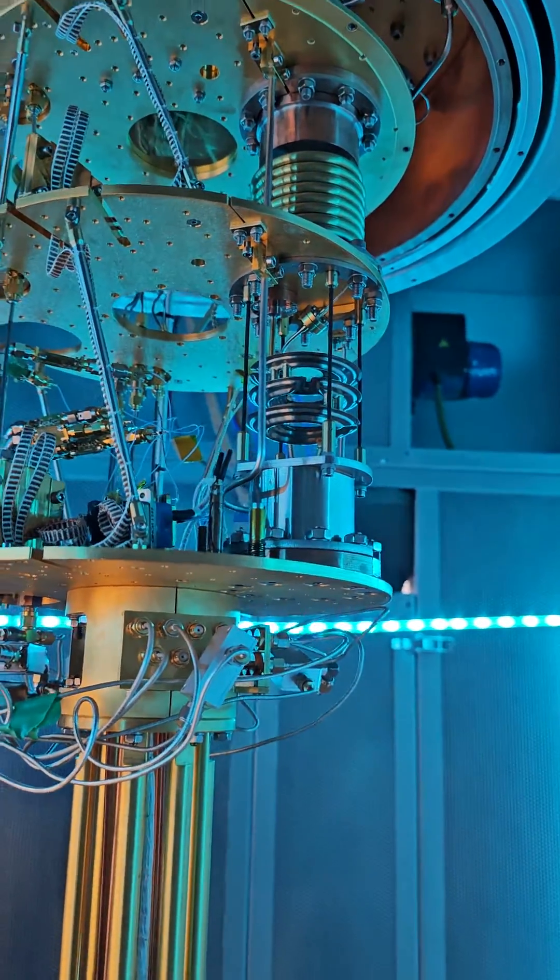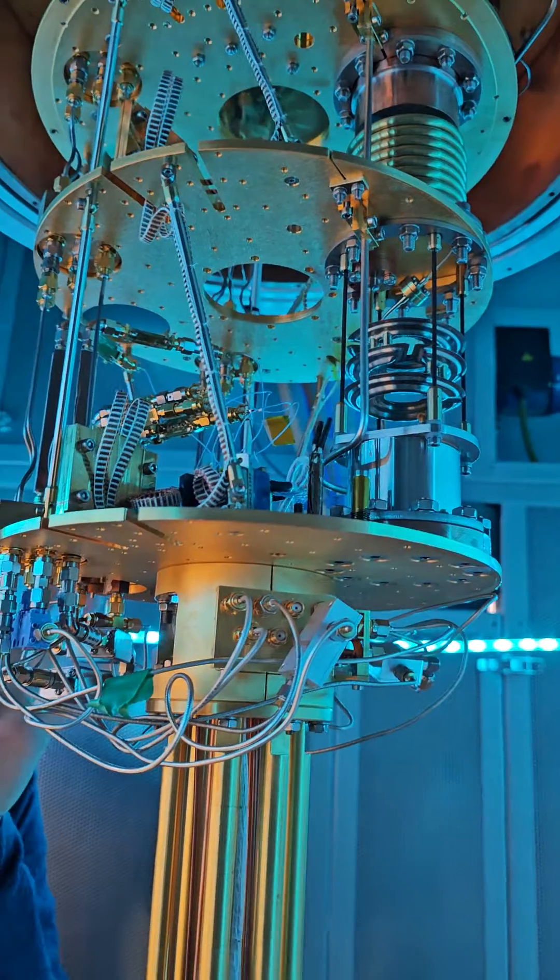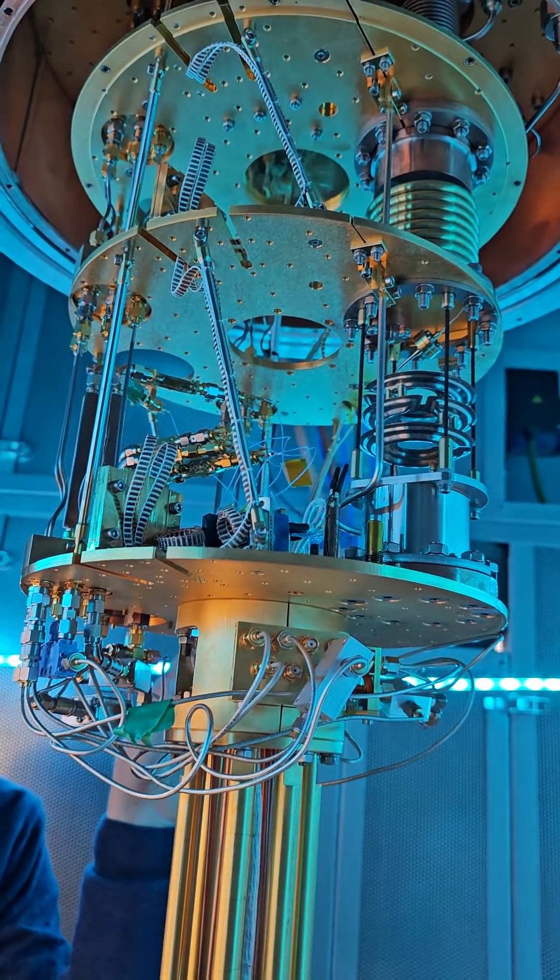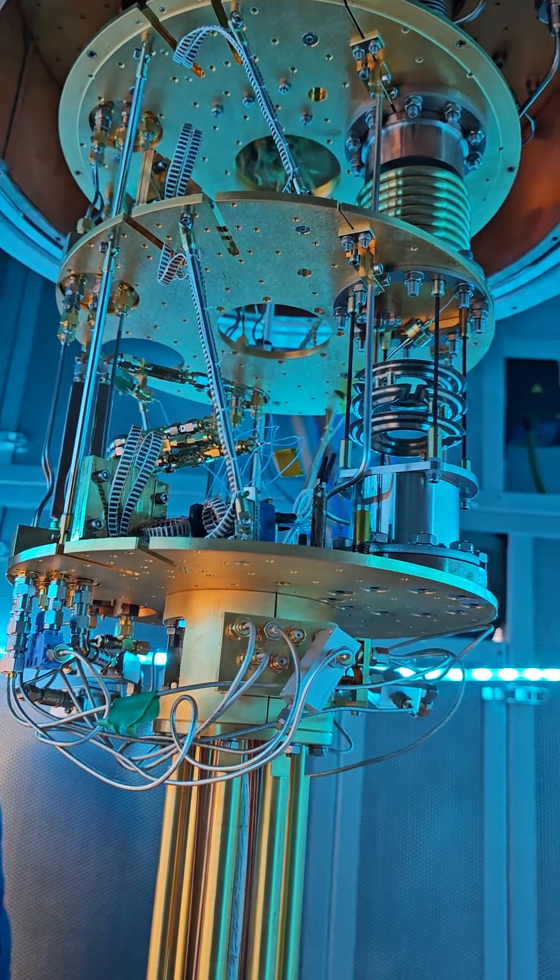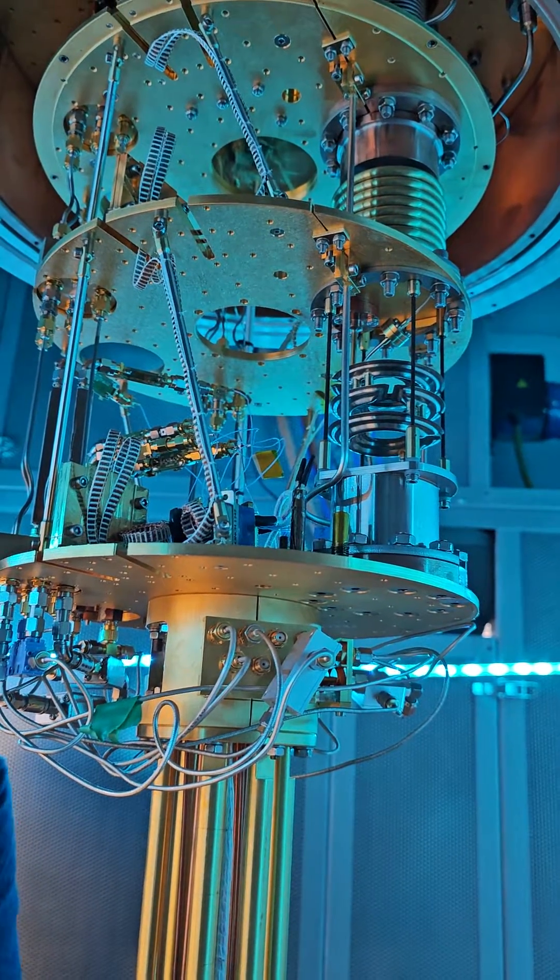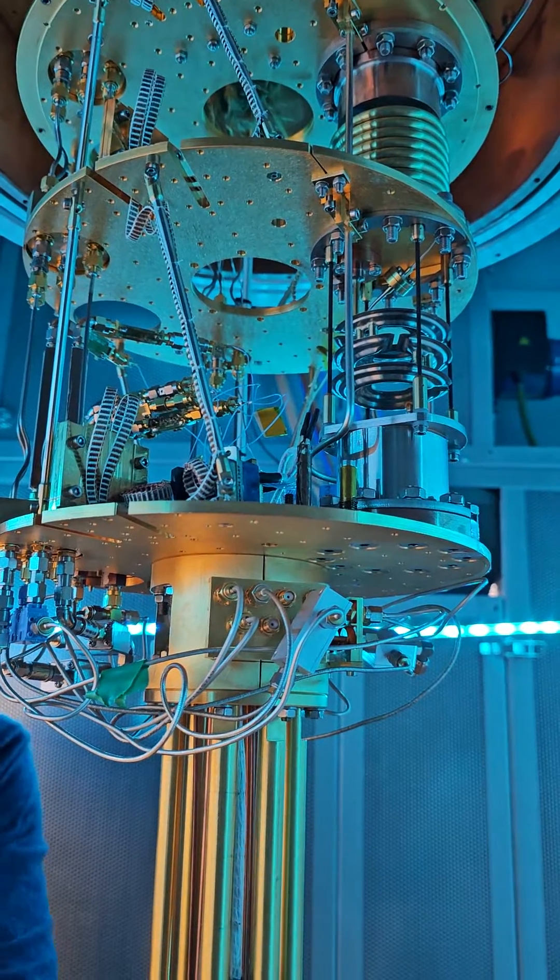It turns out that they had installed high resistance manganin wiring instead of niobium titanium. And because it's copper nickel matrix, you can't tell by the room temperature resistance that you picked the wrong one out of the wrong drawer.